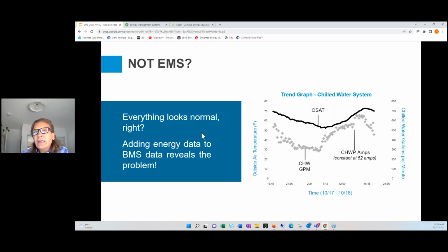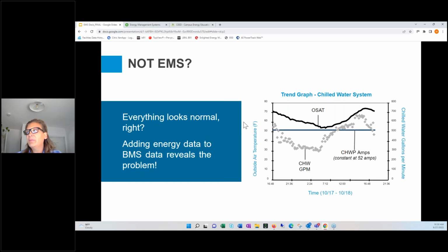Because what we're seeing is as the outside air temperature drops, as it gets colder, we shouldn't need as much cooling, and therefore we should be able to turn down our GPM and not deliver as many gallons per minute to our load. And so that's what we would expect to see. But if we're able to add one more piece of data, our energy data or power data, we have our chilled water pump amperage. And when you see this, you see it's a straight line.